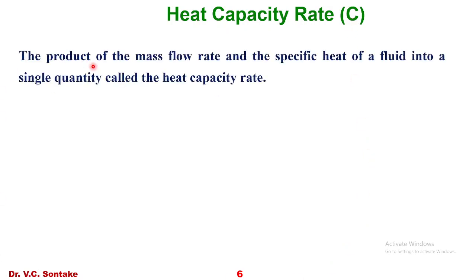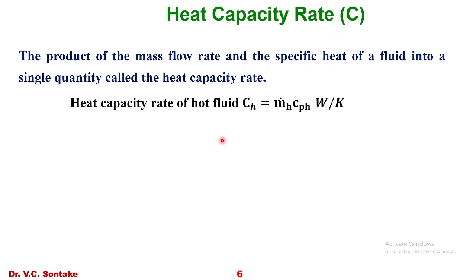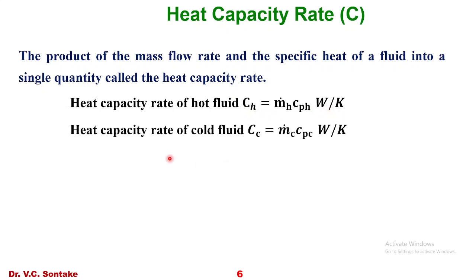The product of the mass flow rate and the specific heat of a fluid is combined into a single quantity called the heat capacity rate, represented by capital C. The heat capacity rate of the hot fluid, C_H = Ṁ_H · C_PH, and the heat capacity rate of the cold fluid, C_C = Ṁ_C · C_PC, both in Watts per Kelvin.